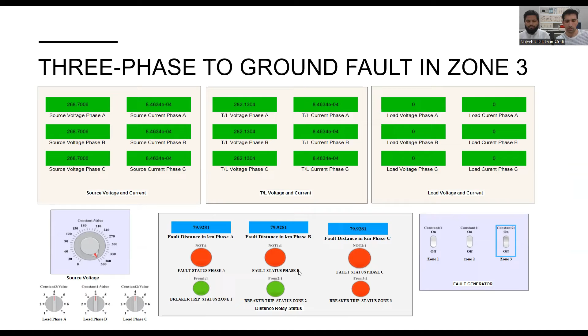Here we give a two phase to ground fault in zone two. So the relay generates a trip signal and isolates the fault. Here we give a single phase to ground fault in zone two, and here we give a three phase to ground fault in zone three, and you can see the relay status. When we give the three phase to ground fault in zone three, you can see that here the system operates normally, and from here the fault occurs and the relay takes 750 millisecond, and then it generates a trip signal.